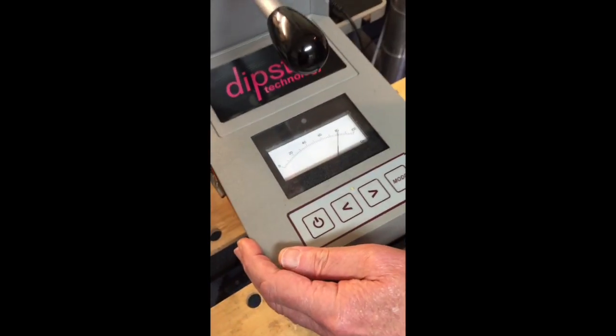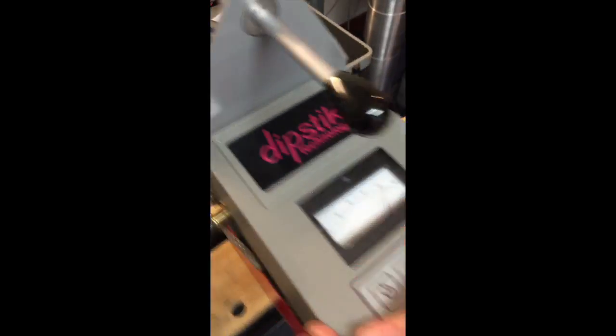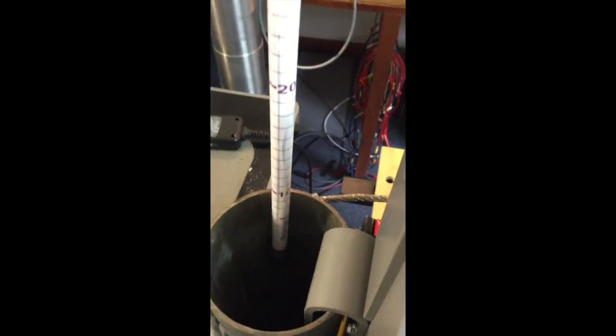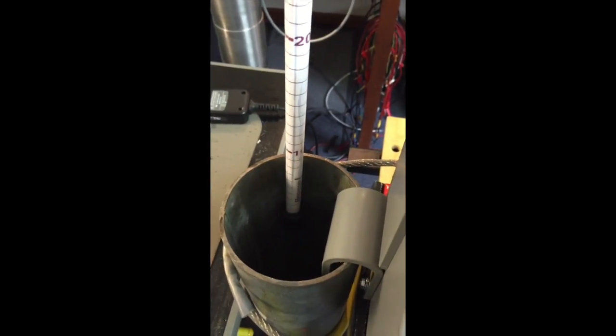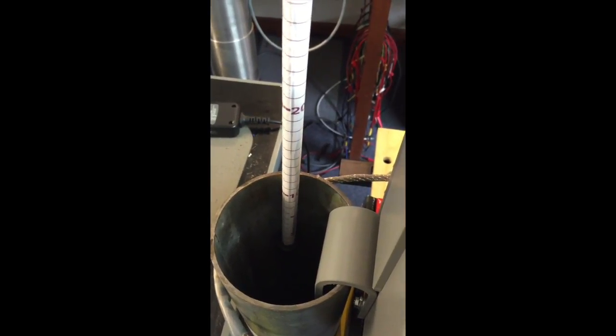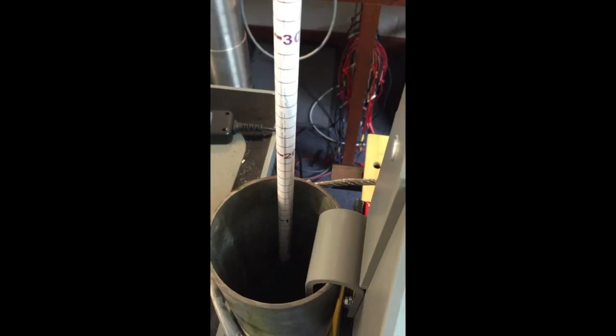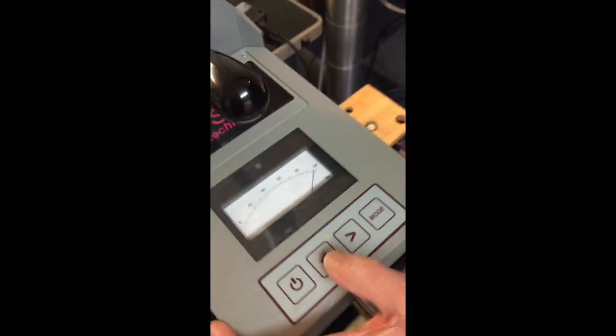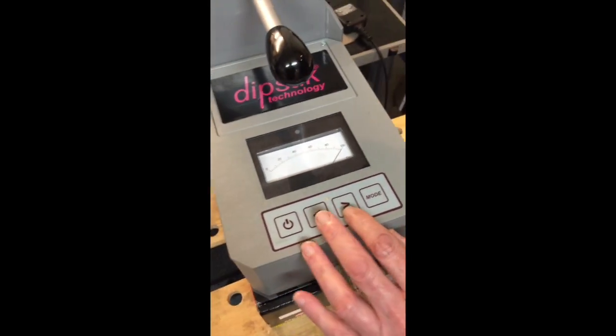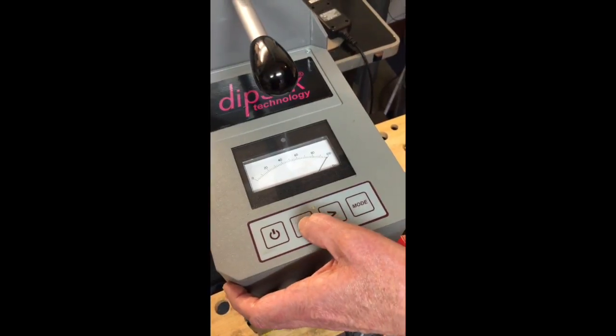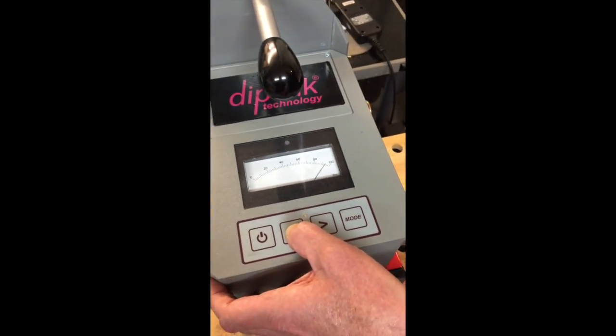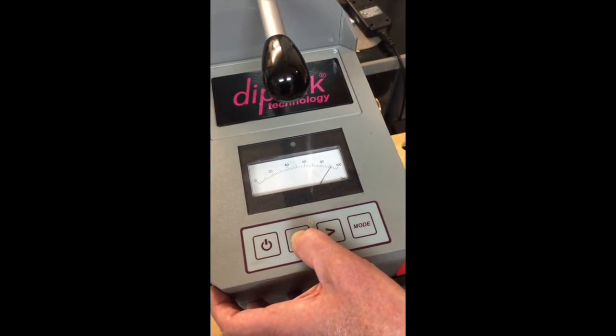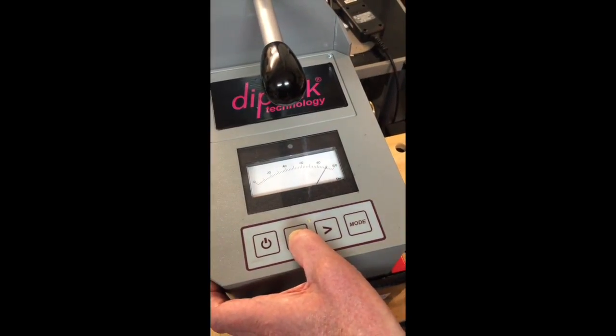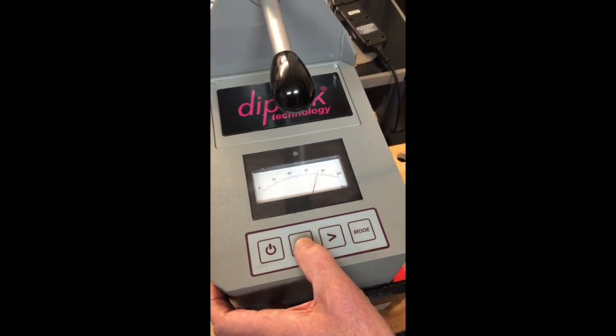So you rushed ahead of me there, Bob. The first thing is to calibrate it, get up to the calibration point. And the calibration point is any point where the column will be at a sensible thickness. At least 2 inches from the coil. That's right. And in order to set the calibration, we again use the up and down keys. What are we setting it to, Bob? We're going to set it to about 100%. It's normal.